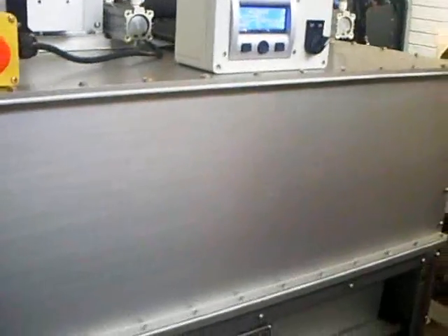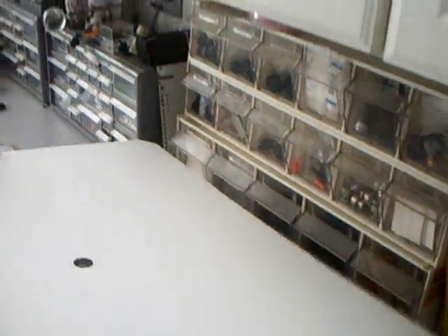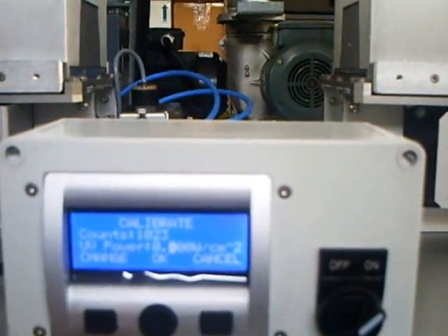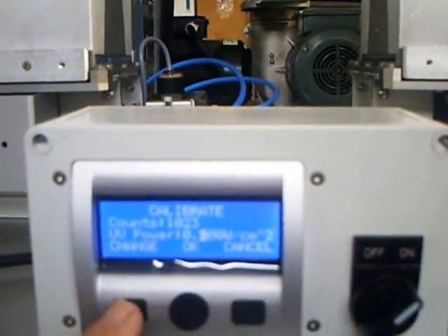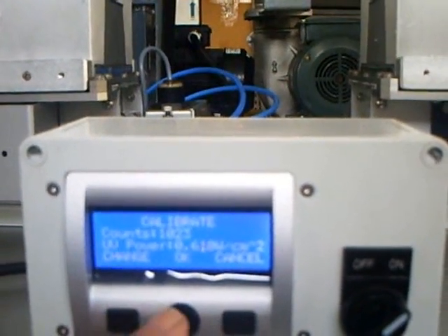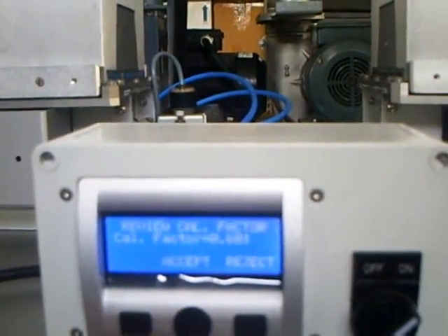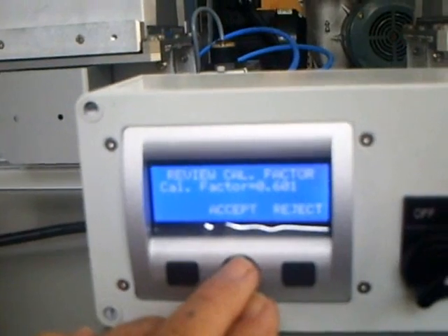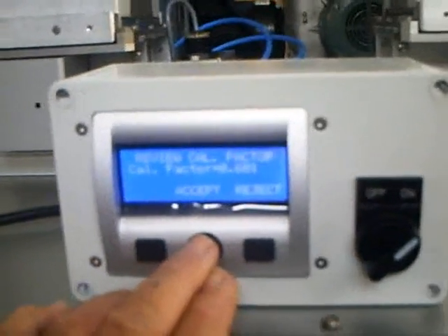Okay, now what we'll do is remove the cake pan with the radiometer. We read the radiometer. What we do at that point is read the watts per centimeter square, which happen to be 0.615. We go over to the UV power here, and we plunk in 0.615, okay, and we accept that, and that is we have calibrated the system.